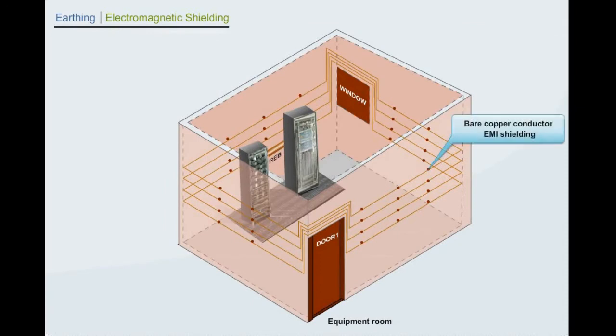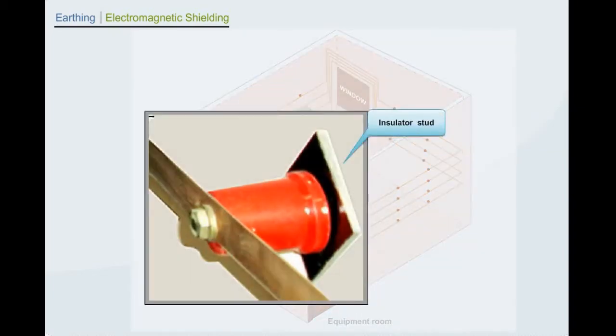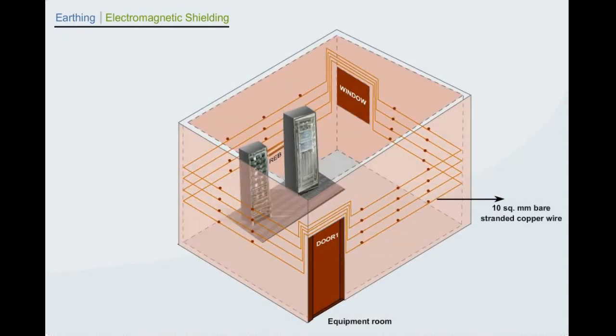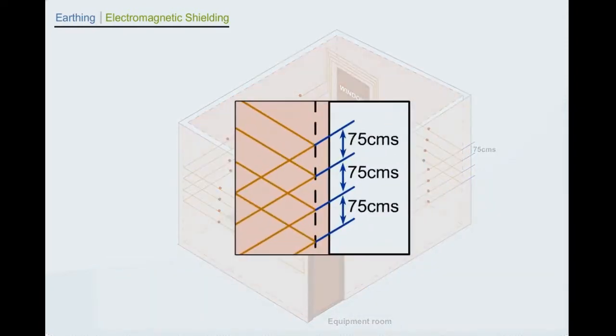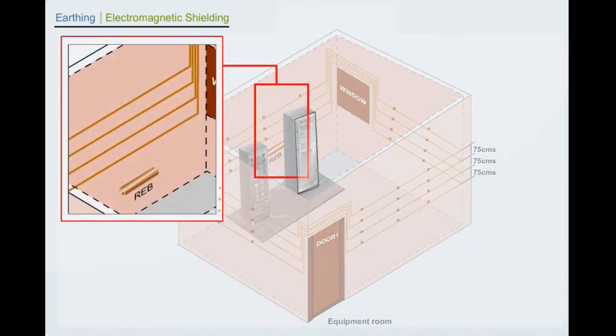EMI shielding is done by using bare copper conductor to run along the 4 walls inside the relay room, and it is placed with a proper insulated stud along the 4 walls. A 10 square mm bare stranded copper wire is used for this purpose. The spacing between the rows must be kept 75 centimeters to arrest minimum wavelength of electromagnetic interference which is being induced inside the room due to distant lightning.